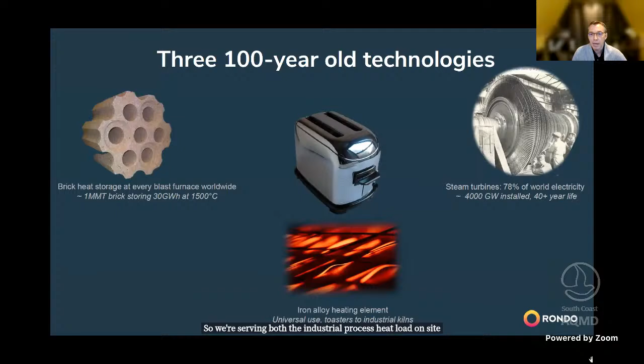Next slide. So in the top right corner, the bricks are stacked. The bright yellow lines there are electric resistance heaters. They hang inside of those bricks. The stack of bricks gets hot. You then blow air through those bricks, and then that hot air blows across the traditional boiler. In our case, we use a heat recovery steam generator. That boiler is the same boiler that you would find in like a combined heat and power gas turbine or in a combined cycle power plant. And then that steam is delivered at really any temperature or pressure, can deliver hot water, heating oil, any other working fluid. Because the bricks get so hot, we're really able to deliver any pressure steam. So some of our earliest applications are delivering 5 psi steam, and then the other one is delivering 1100 psi steam. We can deliver superheated steam, really matching whatever that industrial process is, and also retrofit power plants.